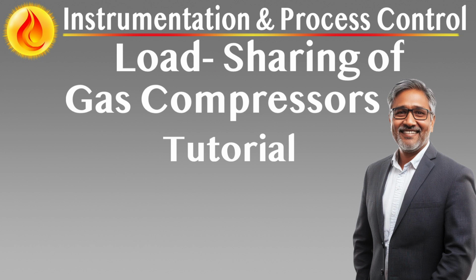Summary. Primary capacity control empowers a compressor network to operate as a unified intelligent system. By distributing a central control response to both performance and protection layers, and letting each compressor determine the most effective local action, this method delivers real-time adaptability, operational stability, and maximum efficiency. Through its strategic role switching and coordinated response logic, primary capacity control enables consistent flow or pressure regulation across complex process environments, serving as the bedrock of safe and effective load-sharing compressor systems.